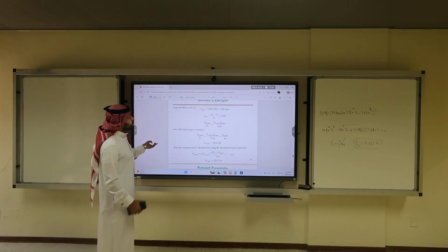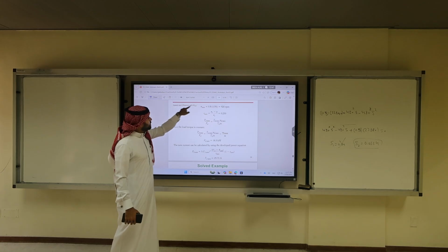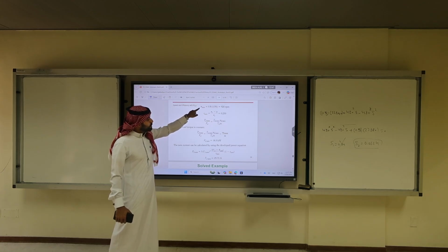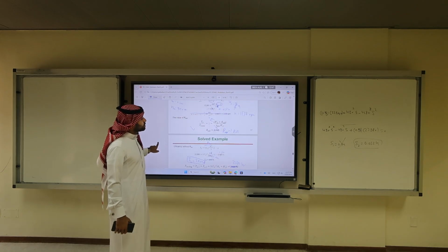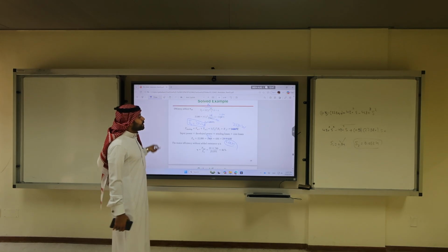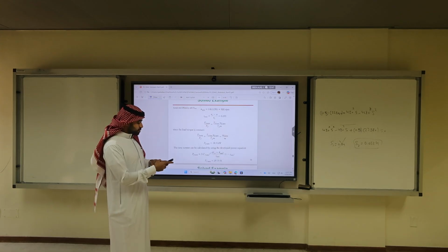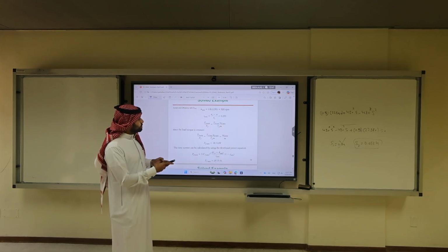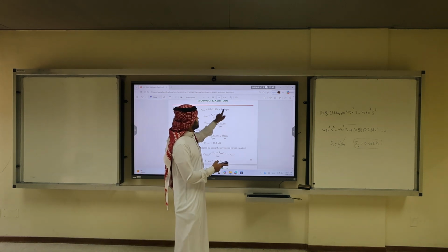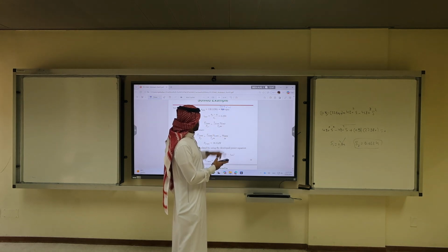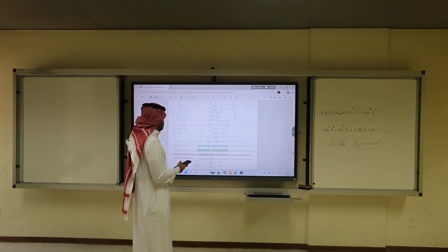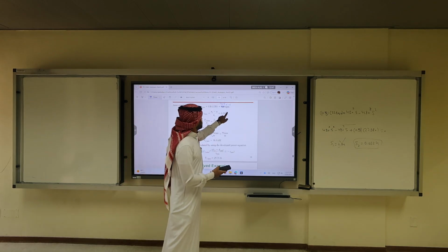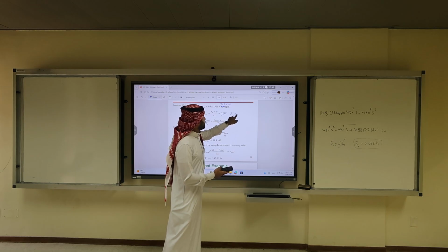If we do the efficiency after adding the R, you now have a new speed, a new slip, which he compared with the speed of 1150, which is wrong. So you need to compare to the speed 1137. So 0.8 times 1137 is 909.6 RPM. We got the slip. We already have it here, 2.42%.